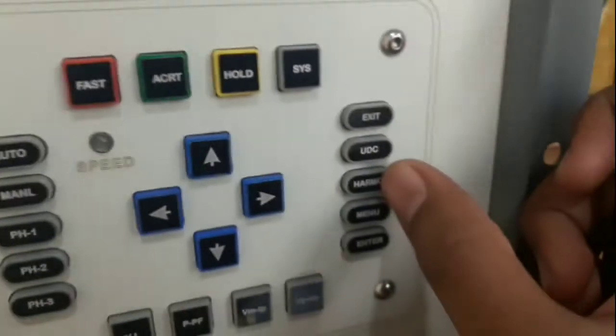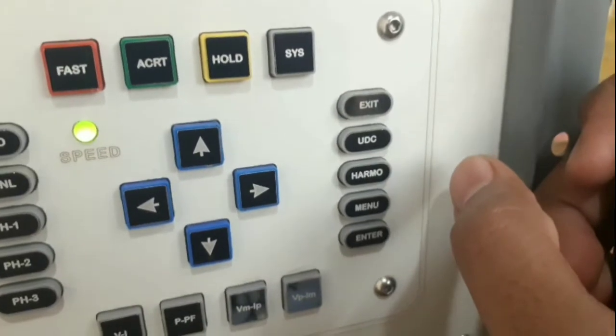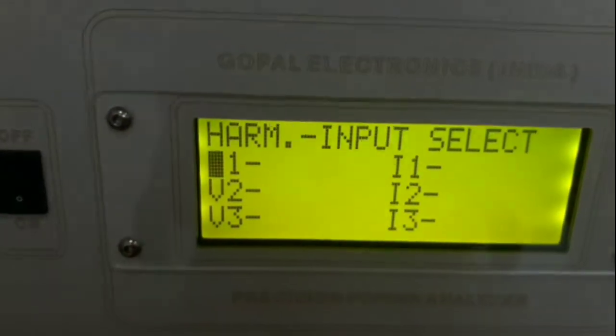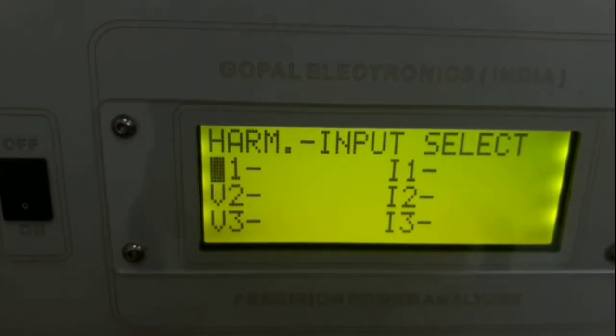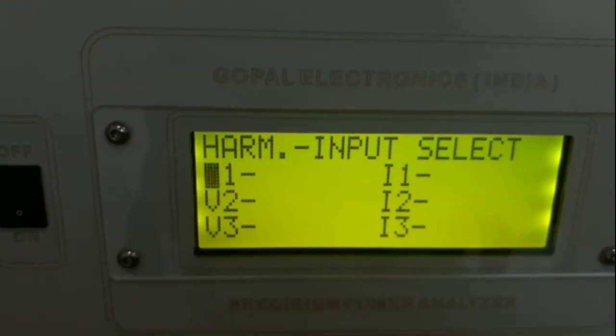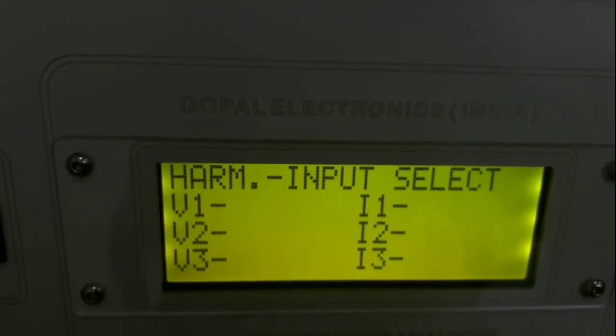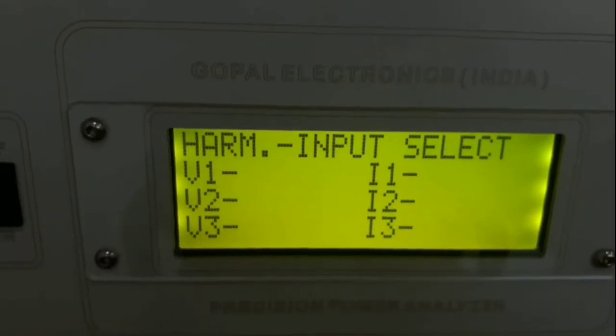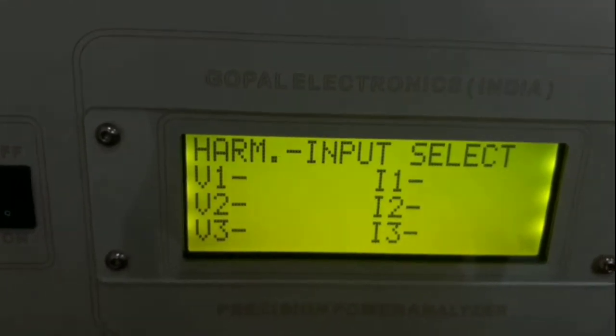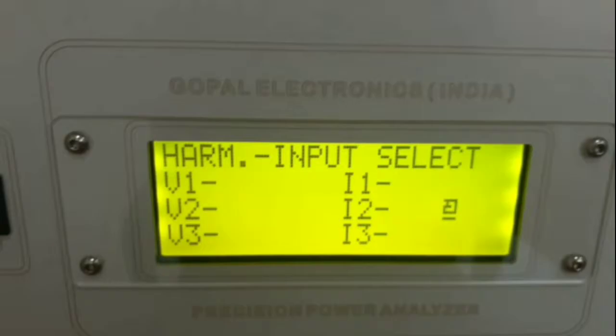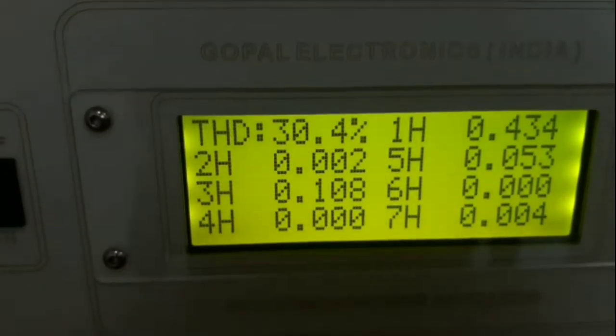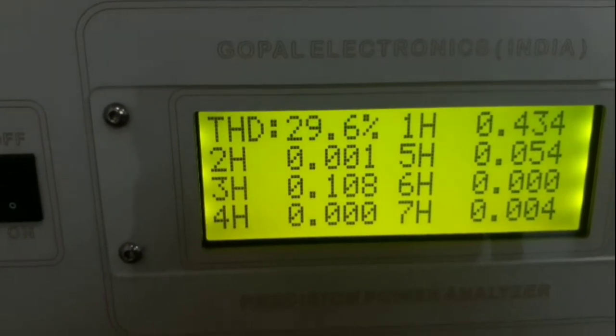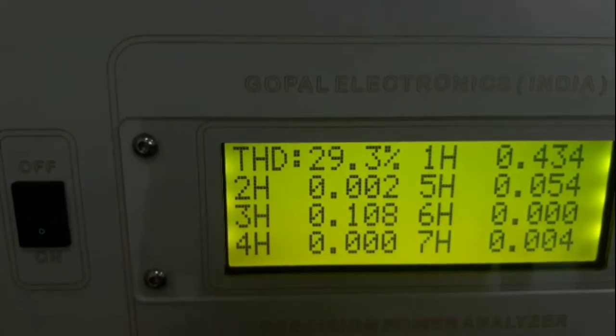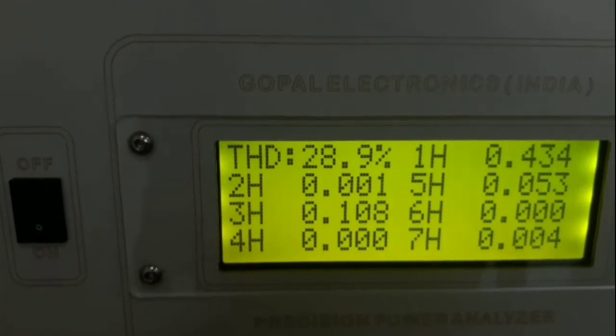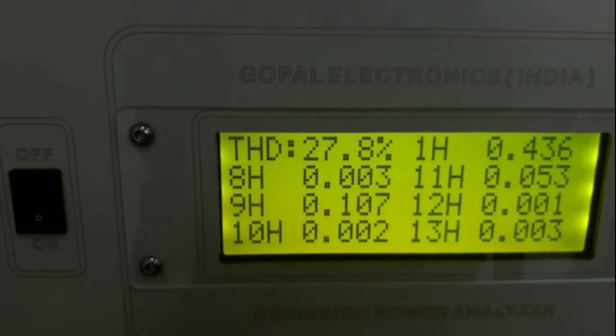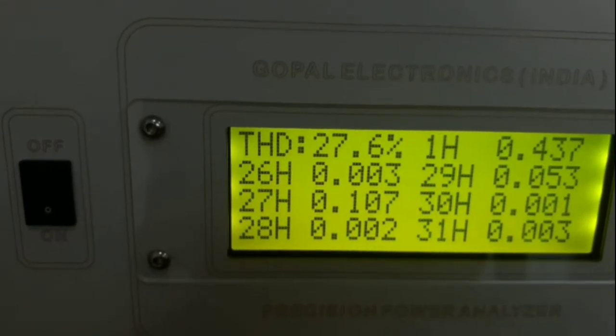Below that key, the harmonic key is given. By pressing the harmonic key, first you can select the parameter of which harmonic you want to see. If you want to see the phase 2 current harmonic, then bring the cursor to I2 and press enter. First it will show total harmonic distortion and harmonics up to 31 order. By pressing the up key you can go up to the 31st harmonic order.